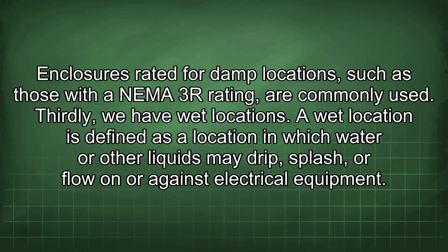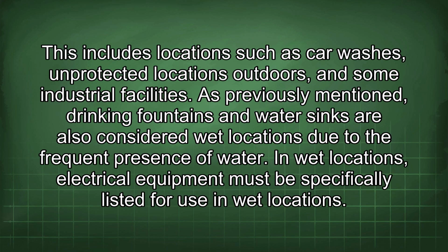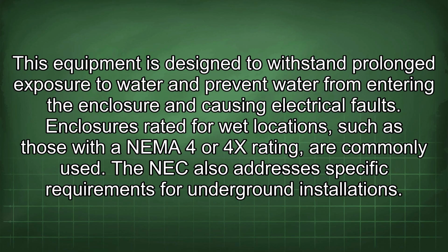Thirdly, we have wet locations. A wet location is defined as a location in which water or other liquids may drip, splash, or flow on or against electrical equipment. This includes locations such as car washes, unprotected locations outdoors, and some industrial facilities. As previously mentioned, drinking fountains and water sinks are also considered wet locations due to the frequent presence of water. In wet locations, electrical equipment must be specifically listed for use in wet locations. This equipment is designed to withstand prolonged exposure to water and prevent water from entering the enclosure and causing electrical faults. Enclosures rated for wet locations, such as those with a NEMA 4 or 4X rating, are commonly used.